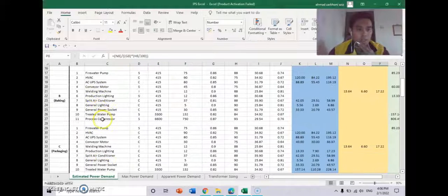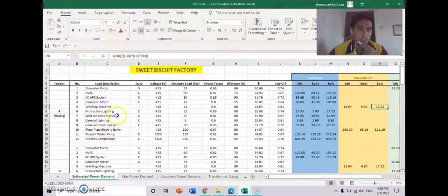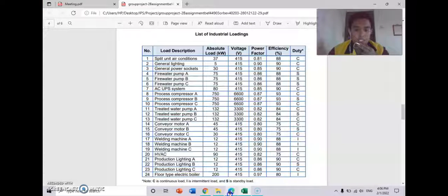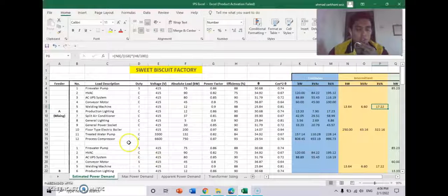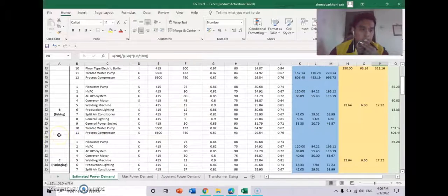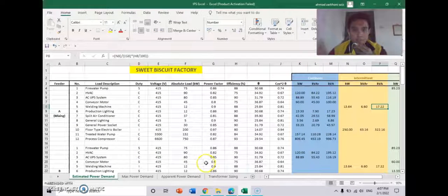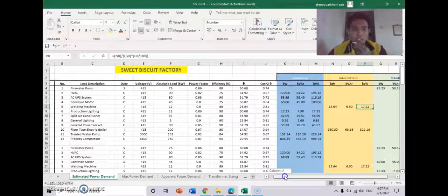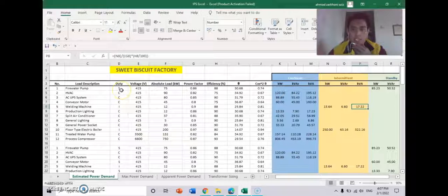I will explain the calculation in Microsoft Excel for this project. Basically, this is the load description for this sweet biscuit factory that has been given in the instruction, which is at least 24 loads. We have divided the loads into 3 feeders: A for mixing, B for baking, and C for packaging. Each load has its own duty: S for standby, C for continuous, and I for intermittent. The calculation uses this formula.